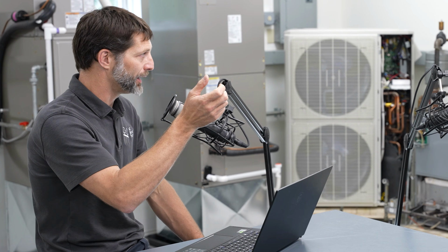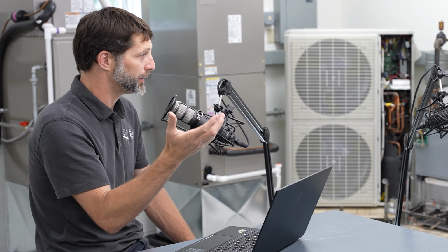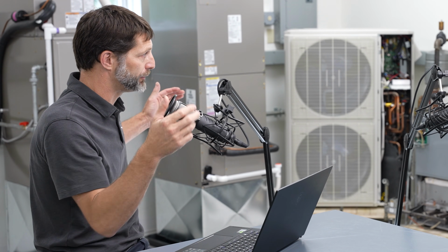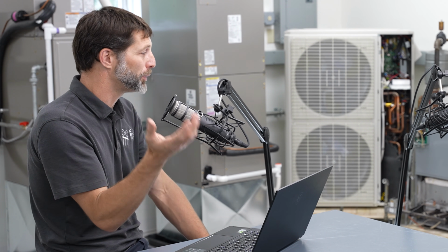So if you just disconnected the bulb from the vapor line, which may have been anywhere from say 32 degrees to 50 degrees Fahrenheit, or it just depends on the heat load inside the building at that point in time. When you remove that, now it's sitting maybe within a 70 degree inside of the building, right? If it's in a closet, if it's up in the attic, maybe it's 120 degrees up there. And so like you said, it's going to apply more opening force on the head of the TXV, and it's going to allow more liquid refrigerant in because it thinks that there's a crazy high heat load, meaning the temperature of the air crossing that indoor coil. And the TXV's job is to maintain superheat, not to maintain the vapor pressure.